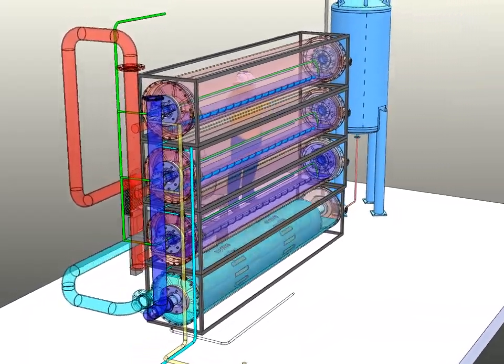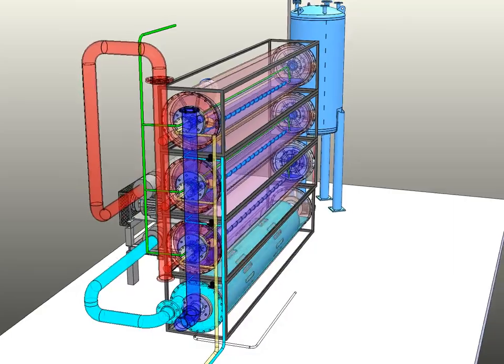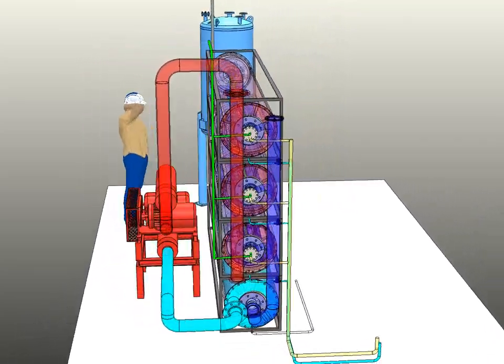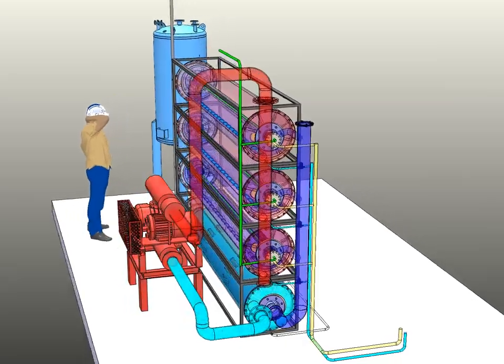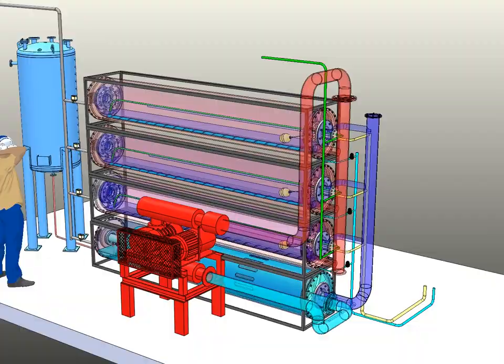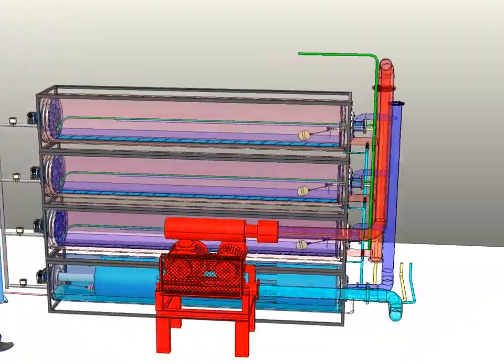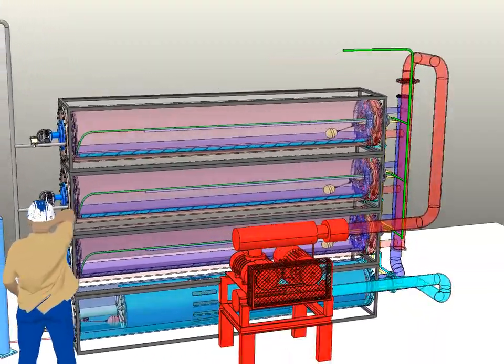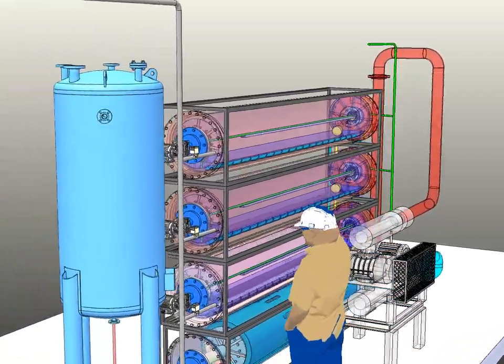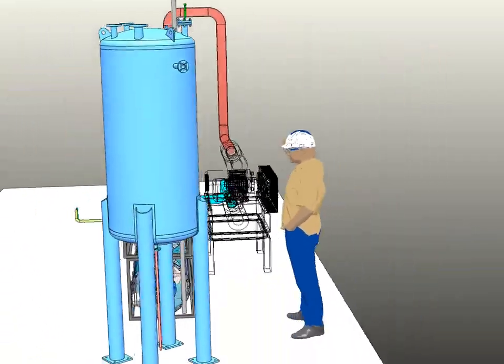The module of a horizontal packed mass exchange apparatus located in the lower part cleans the contaminated steam from aerosols. This module contains a drum packing device, the lower part of which is immersed in reflux. Purified steam from the module with a rotating annular bed of nozzles is fed through the steam pipeline to the roots pump, where it is compressed, heated and the cycle is repeated.